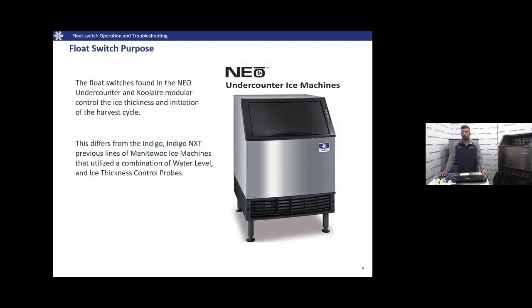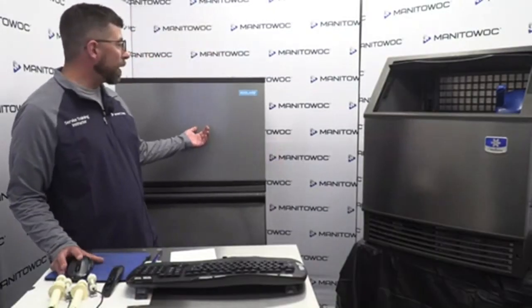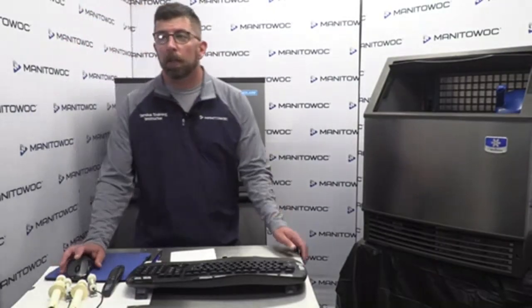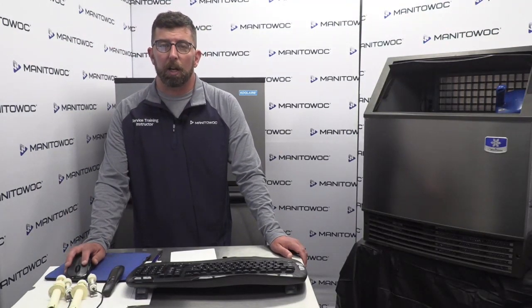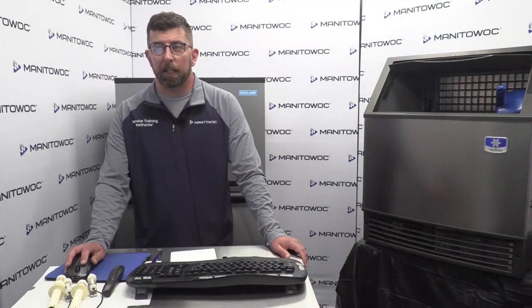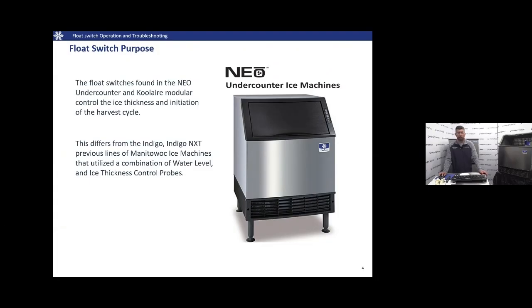The main topic today is float switch purpose and troubleshooting. Our NEO undercounter ice machines and the Koolaire modular units utilize float switches to control ice thickness and to initiate the harvest cycle. This is a little bit different from our Indigo and Indigo NXT machines and all previous lines of Manitowocs that typically utilize a water level probe for water level and trough fill, and an ice thickness control probe to initiate the harvest cycle.